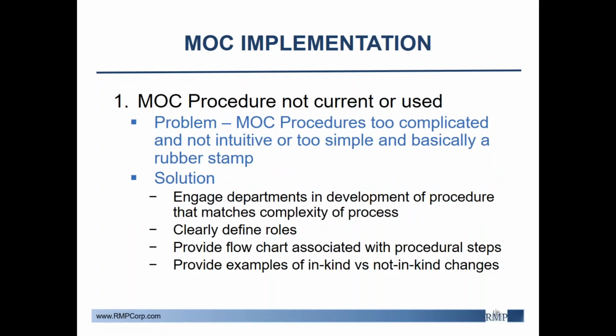So the first one is MOC procedures not correctly implemented, and some common issues include confusion regarding like in kind. For example, facilities often consider changing a pump to a slightly different pump a like in kind change. However, this is not the case. For it to be considered like in kind, it needs to be the exact same pump type. Therefore, for this situation, an MOC must be completed.